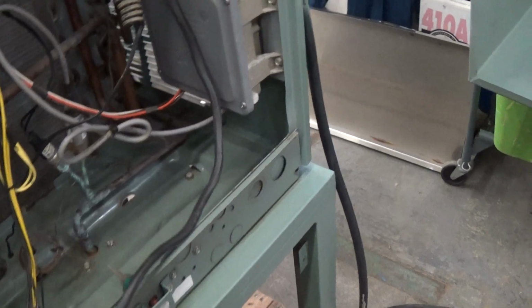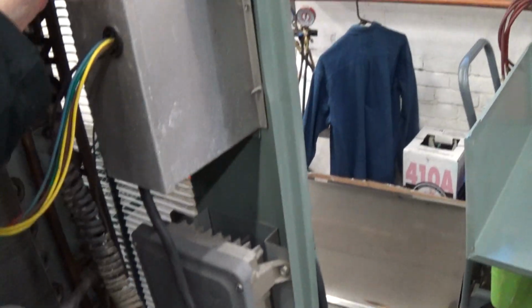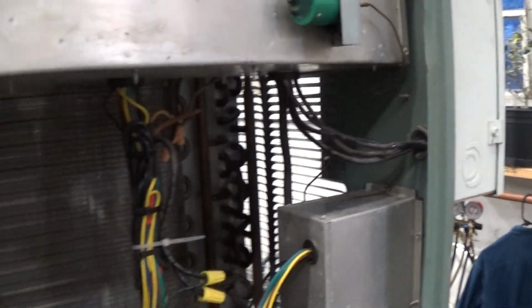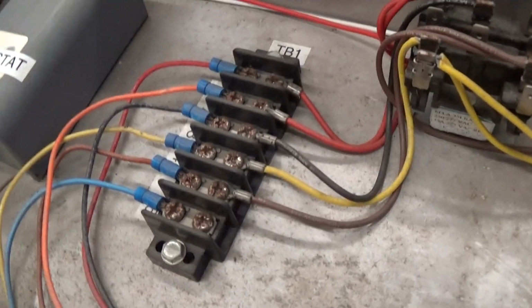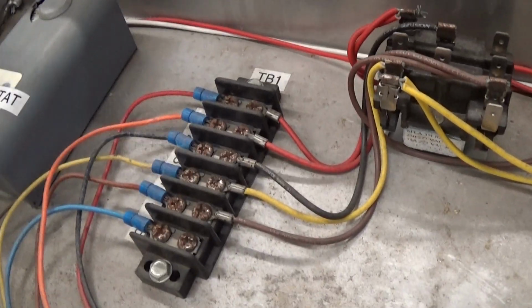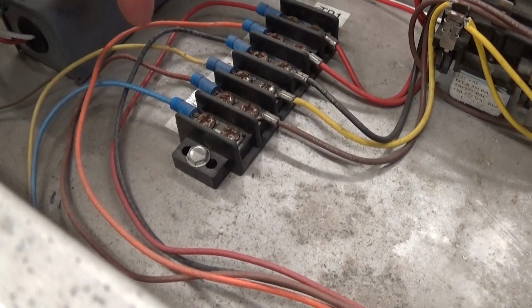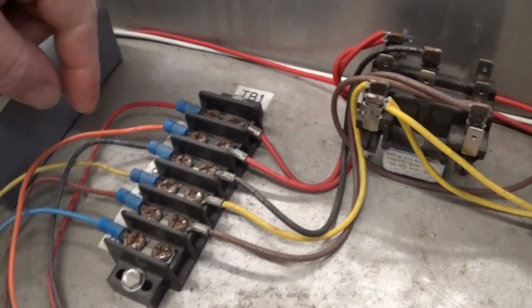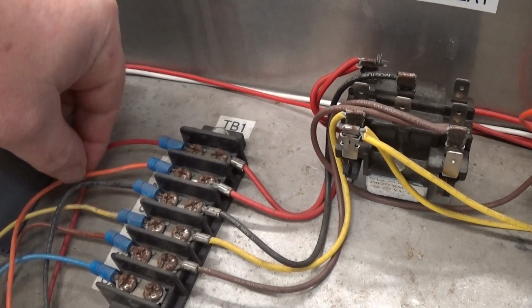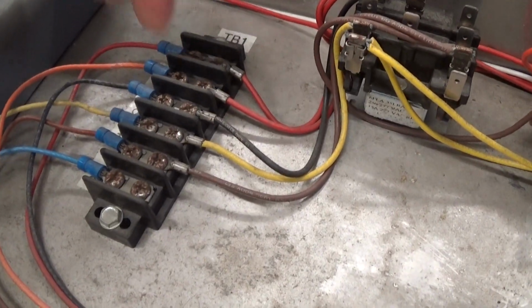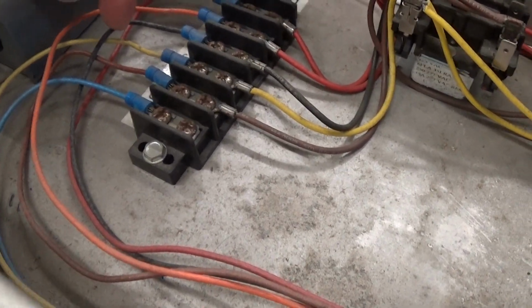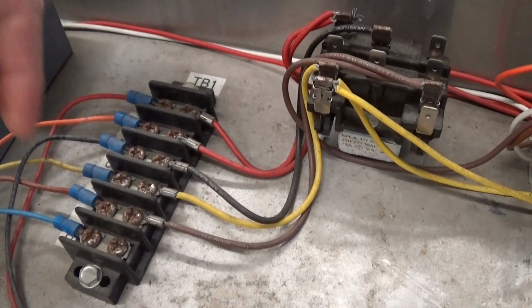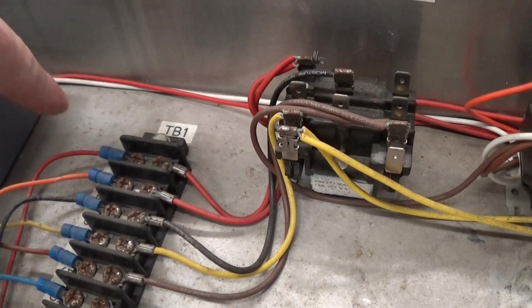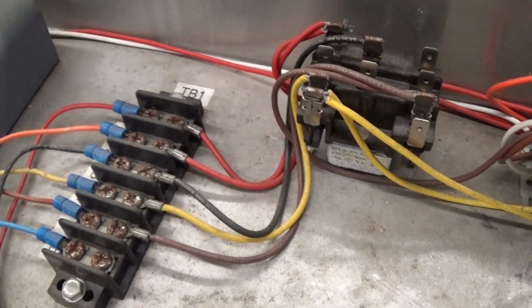But that remote cable comes up here into the controller area, and that comes right to this terminal block right here. And there's 6 connections. It should be pretty obvious. The orange to orange is a little bit questionable. We'll probably mark that. But the black to black, yellow to yellow, brown to brown. We'll disconnect that and make sure it's clearly labeled.